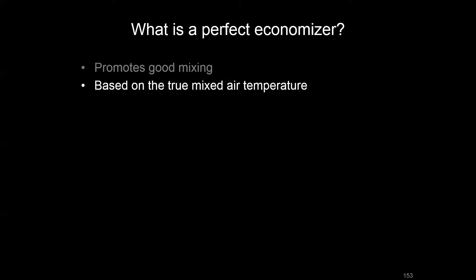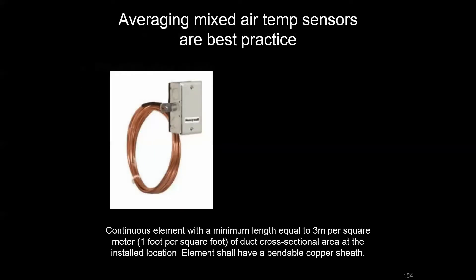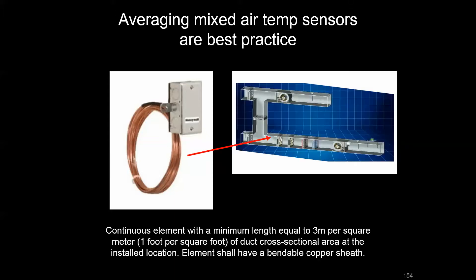In this perfect economizer, we really want a true mixed air temperature to be able to make decisions on. Best practice would be to have an averaging sensor in your mixed air plenum. Our unified facility criteria doesn't specify that we must use averaging sensors for economizers, but where we do use them there's criteria about what that should look like.